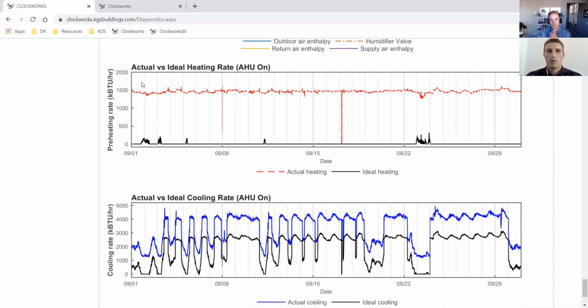So in this case, we're modeling an ideal heating rate of 0. That's pretty easy, right? The valve should be closed. You really shouldn't be heating at any time because you have leak by, because we can detect a delta T across this coil, and because we know the airflow on the unit, we can actually calculate the energy that you're adding into this airstream from that leaking valve, that leaking preheat valve.